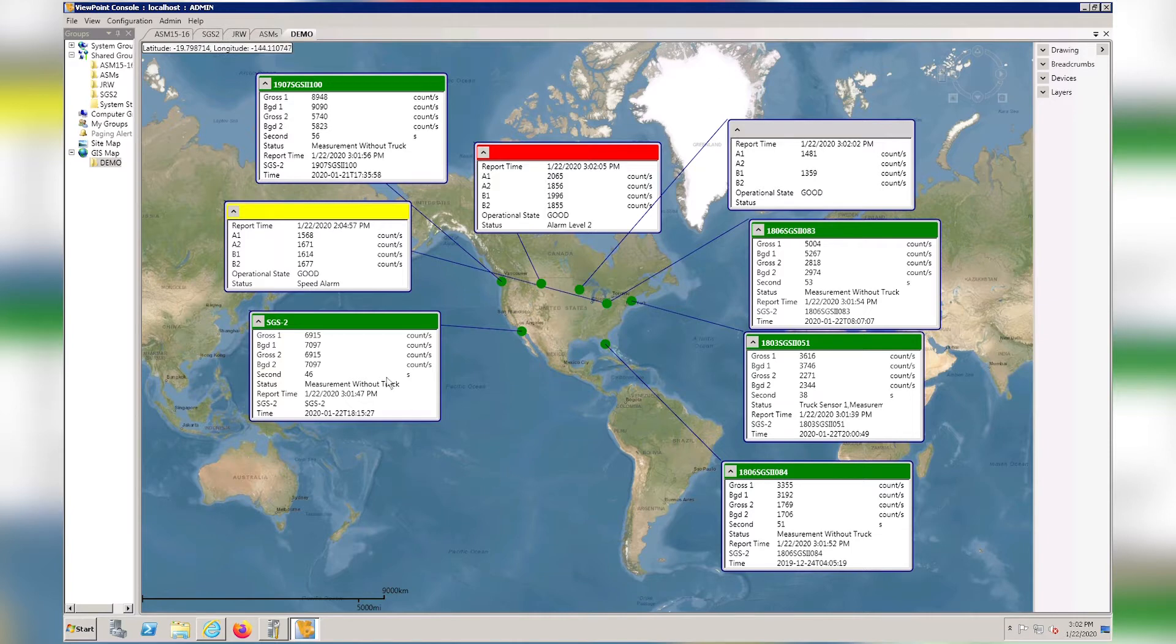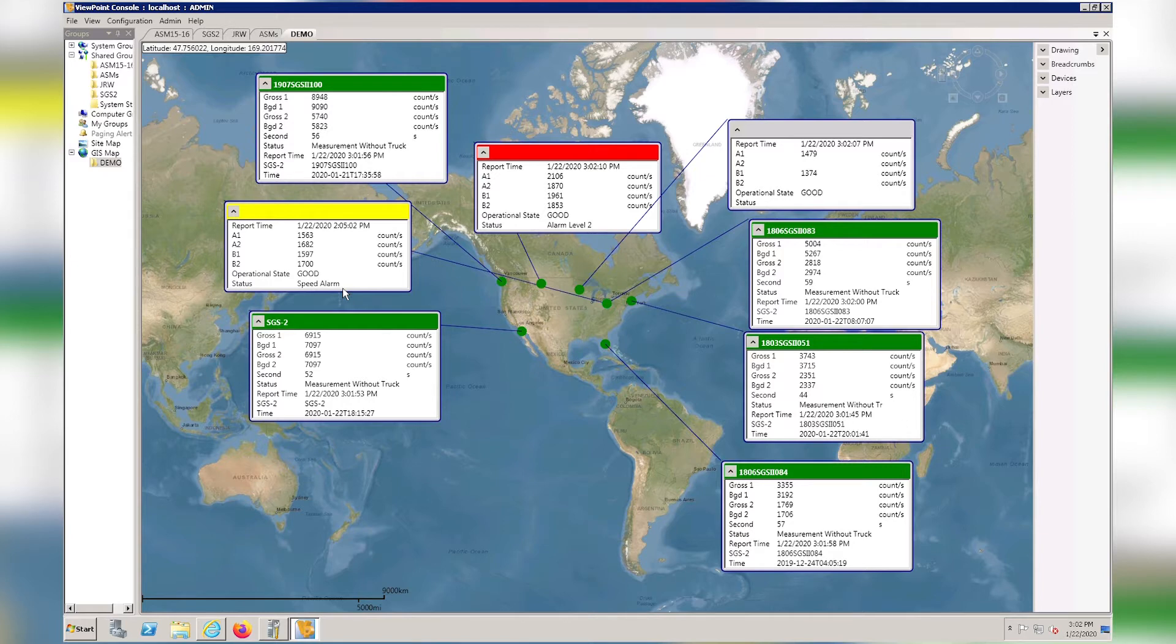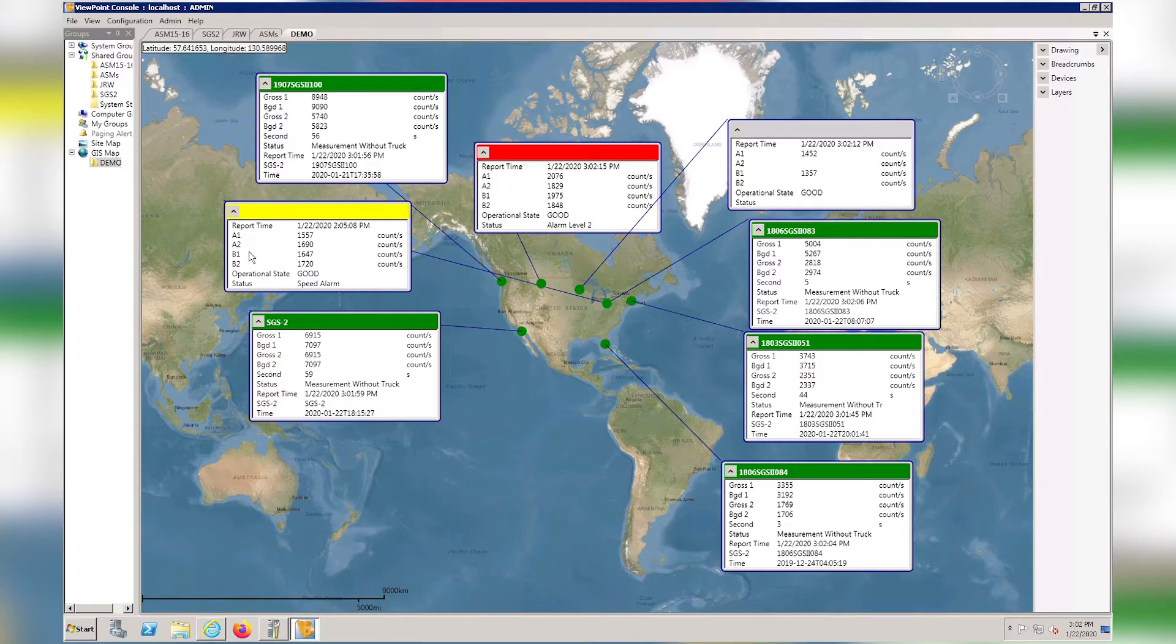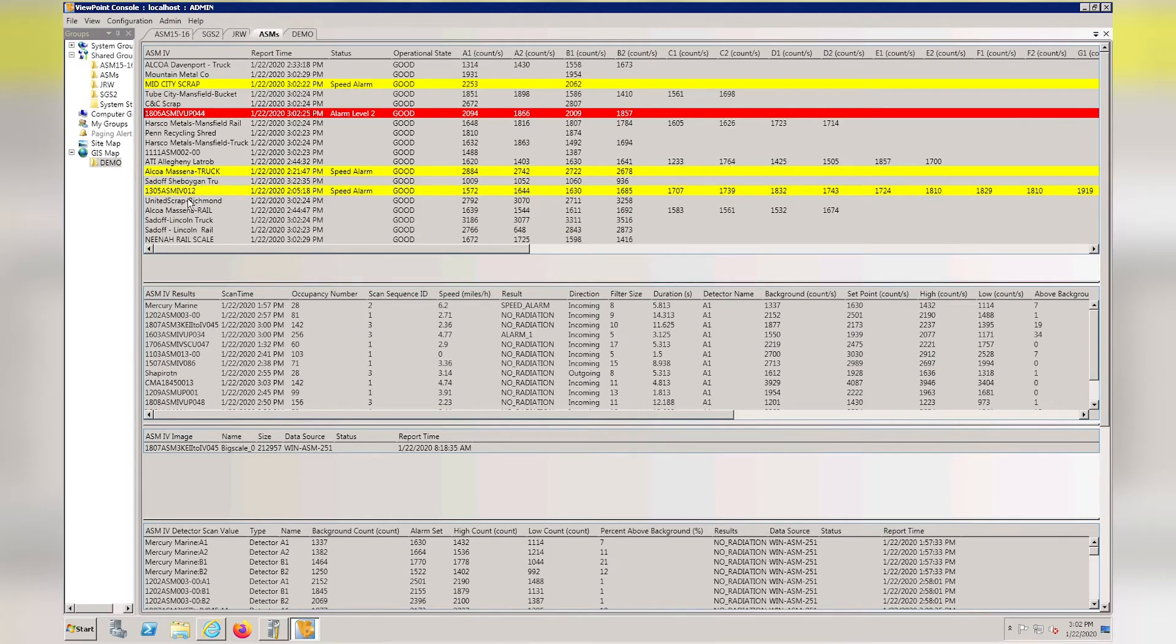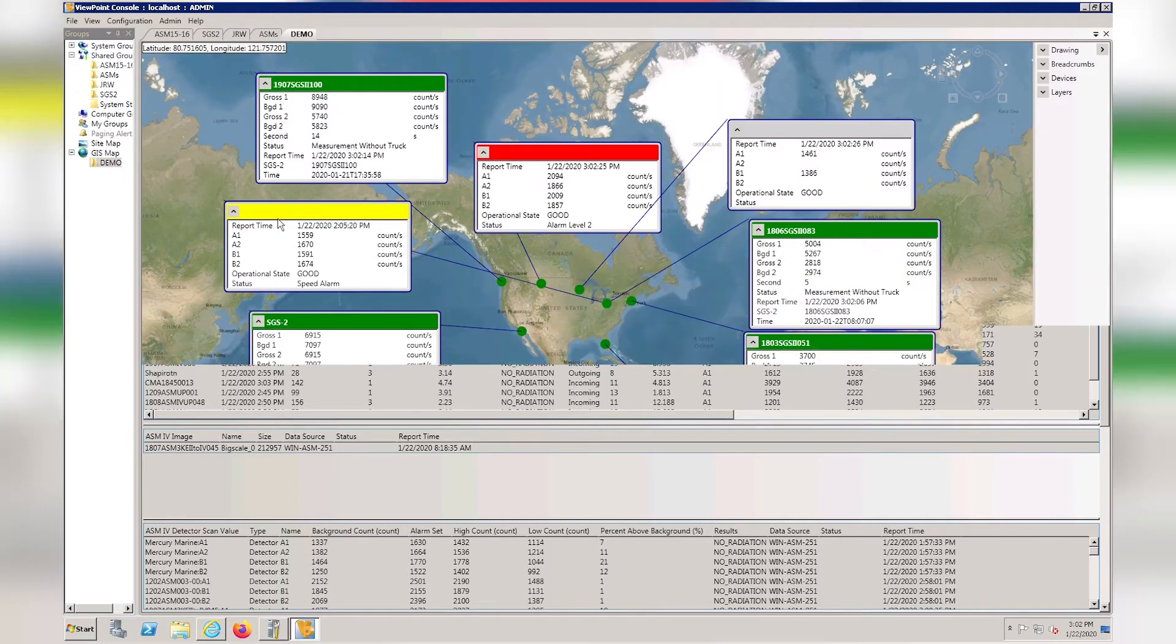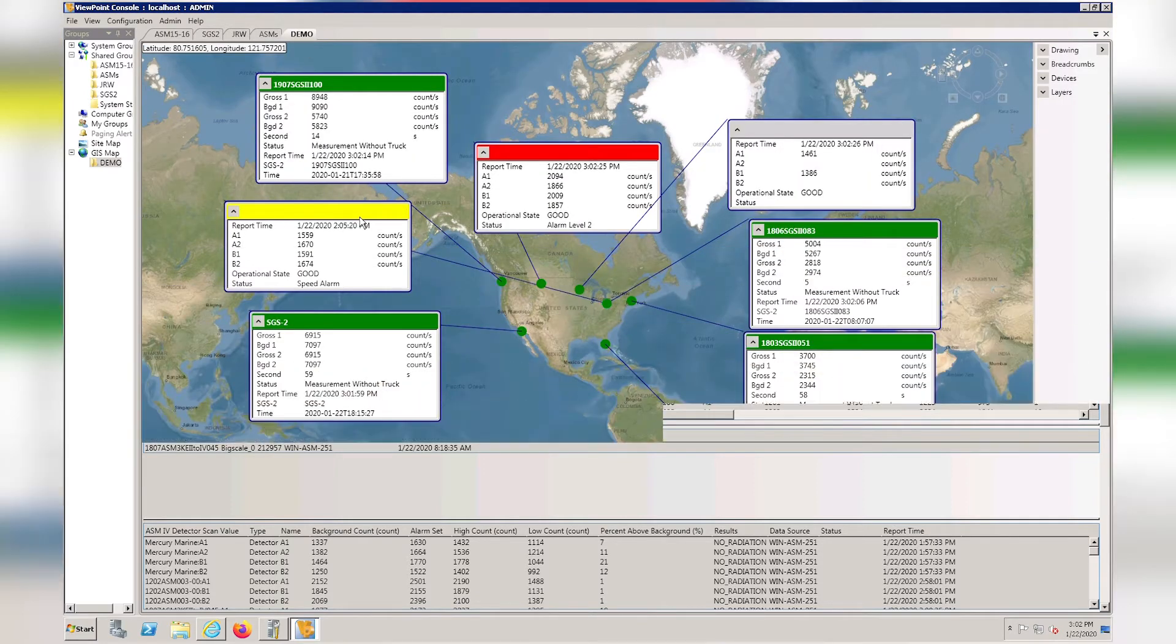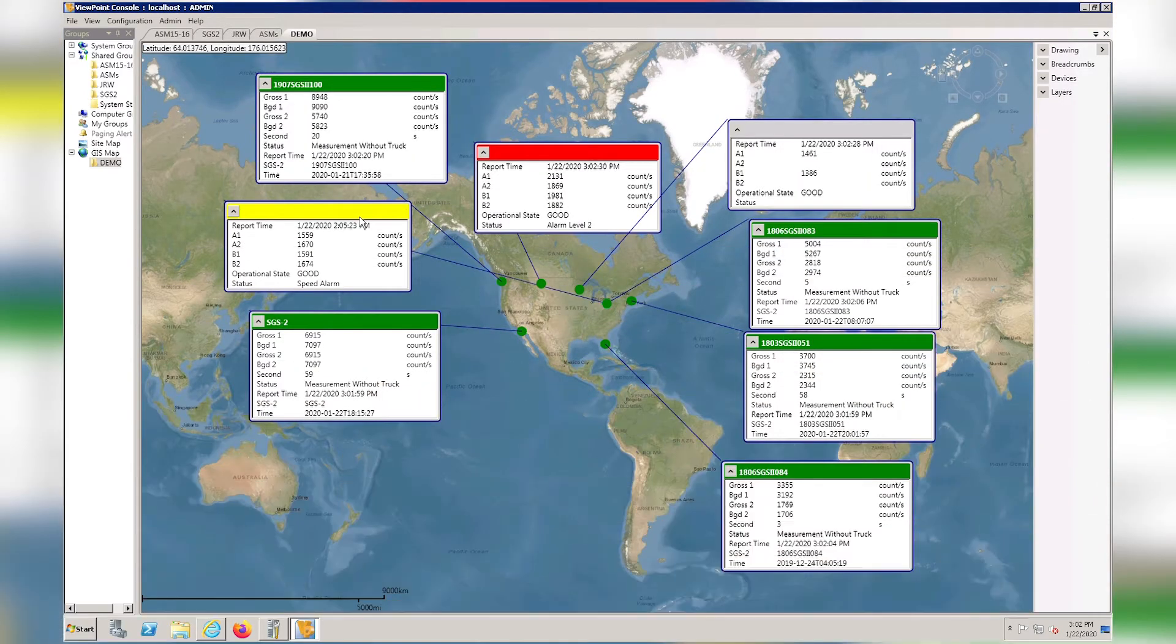If we look at the window with the yellow banner display, it actually corresponds to the speed alarm that's shown on the ASM tab. We can tell that this unit is an ASM because it has an A1, A2, B1, and B2. If we click on the ASM tab, we can see that one of these is in a speed alarm, and it's this one right here. The yellow banner at the top of the window indicates that it's a speed alarm.